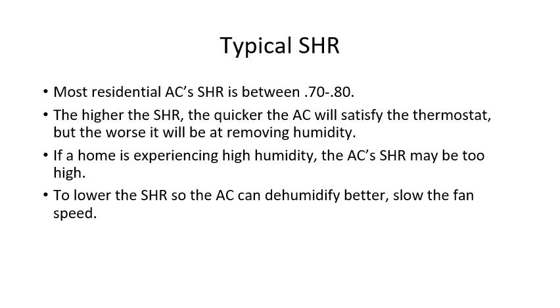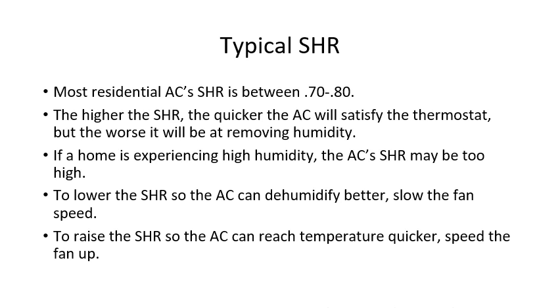What can you do? In order to lower the sensible heat ratio, or make the system better at dehumidifying, you can slow the fan speed down. To raise the sensible heat ratio so that the air conditioning can reach temperature quicker, we can speed the fan up.